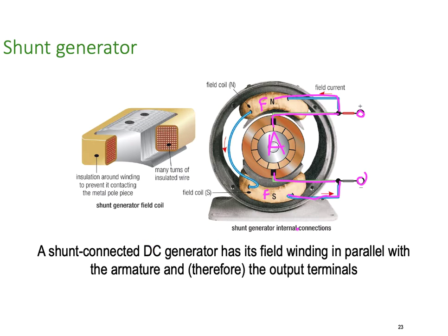So a little bit of the current generated in the armature gets fed from the armature up into the field, which produces some flux, which then produces some more voltage, which produces some more current, which produces some more flux, which then produces some more voltage, which produces some more current. Again, can you see where I'm going? And that produces some more flux, so on and so forth, until the magnetic fields are saturated. And that's how it works. But it requires there to be residual magnetism already in the machine.